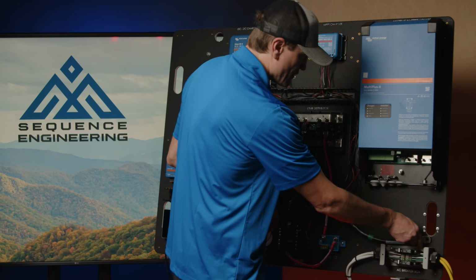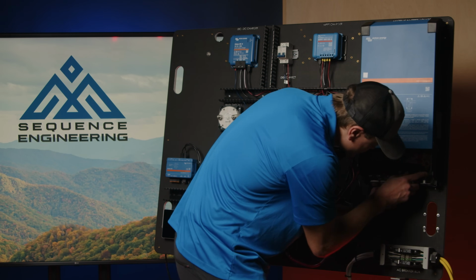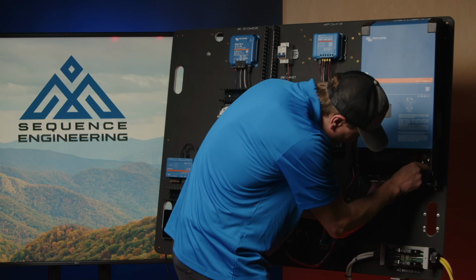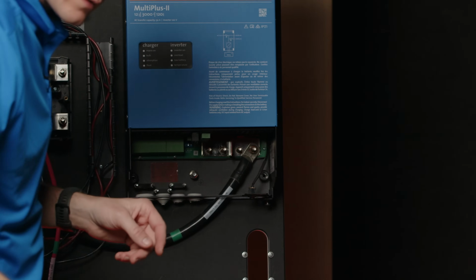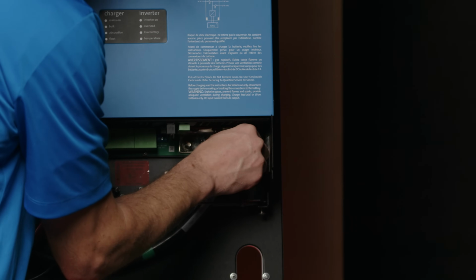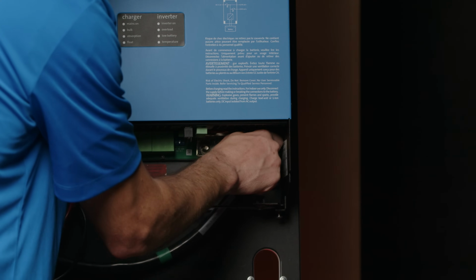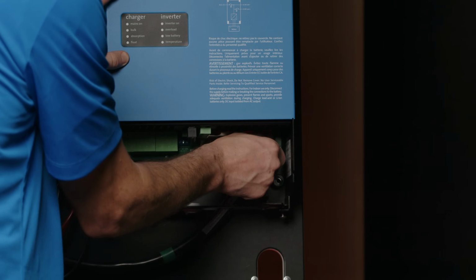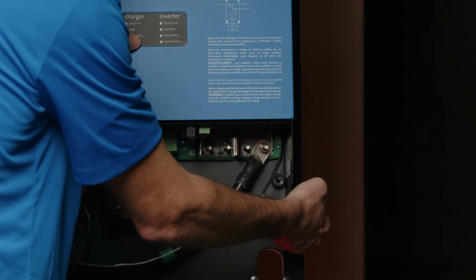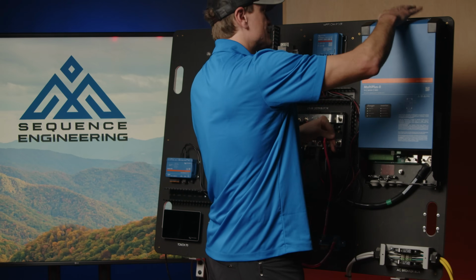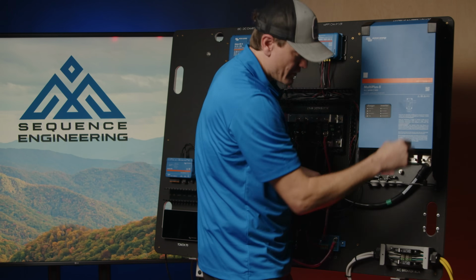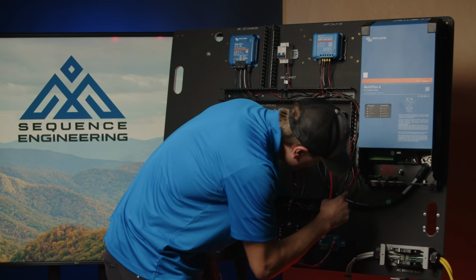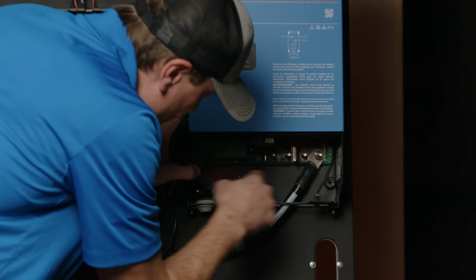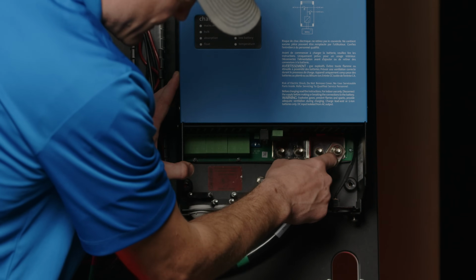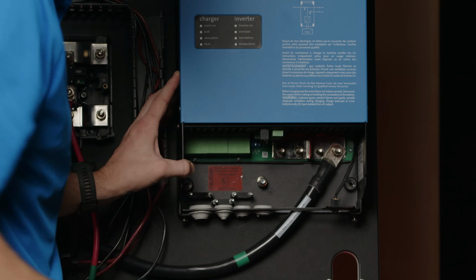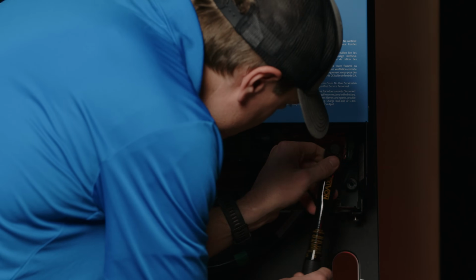Now we're going to move over here and make our Multiplus connection, putting it on this stud here. As I make this connection, I'd like to point out that when I put that cable on the Multiplus, you probably saw it rock like this a little bit. That's because it's connected up here on the mounting bracket, but not down here - there are two other mounting feet down here, here, and here. Once I finish this negative connection, I'll go ahead and throw two screws in so you can see that process.